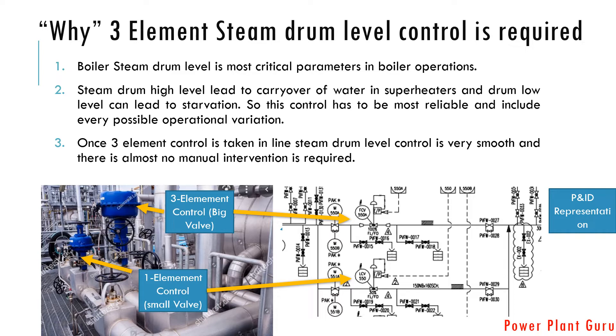Both ways it is very critical and risky, so maintaining drum level is very important for boiler operation. For boiler operation, two different control valves are used — one is smaller and one is bigger. The smaller one is used in startup and shutdown, and the bigger one is used in normal operation. In some plants you may have one small and two big valves. The small one is also called the 30% control valve, and the big ones are called 100% control valves.